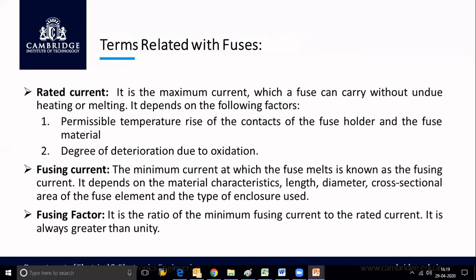So we said when the current in the circuit is more than the rated value, the fuse melts. So always we are talking about rated. What is meant by that rated current? It is the maximum current which a fuse can carry without undue heating or melting. So without any problem, the fuse can carry some amount of current. That current is known as rated current, which is also known as full load current.